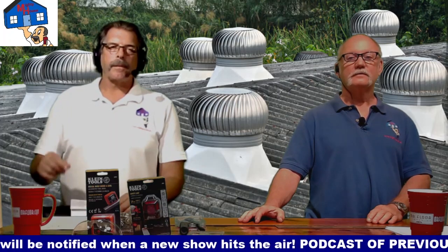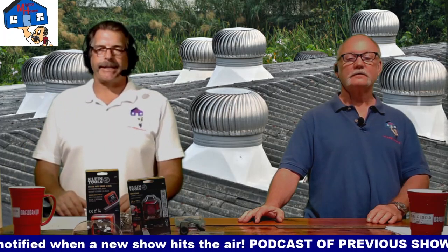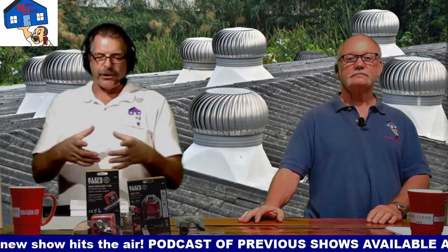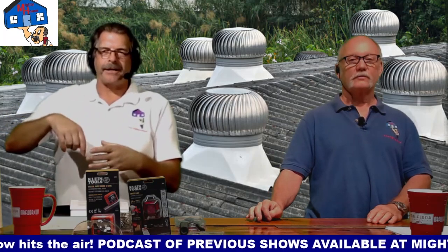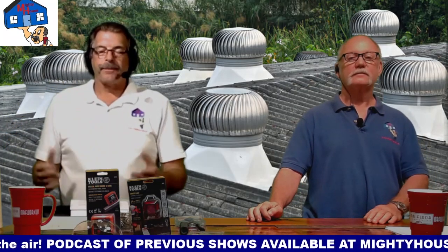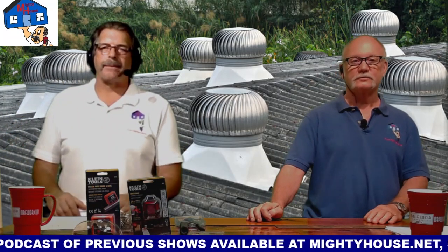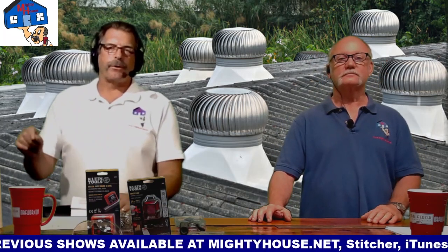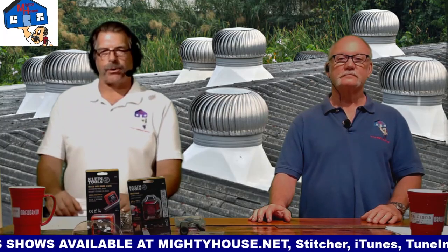Okay. If you have a good solid ceiling, maybe you don't have a lot of can lights, maybe you've got, you know, when the light fixture comes and it has that insulation thing in it, right? And you have that installed, there you go. That's what it's for. It stops air movement. So what you're doing is now you only need one square foot of venting for every 300 square feet of attic.